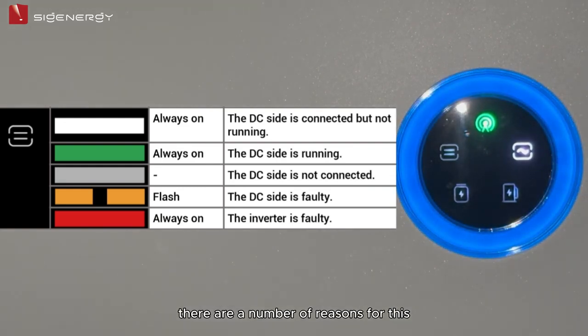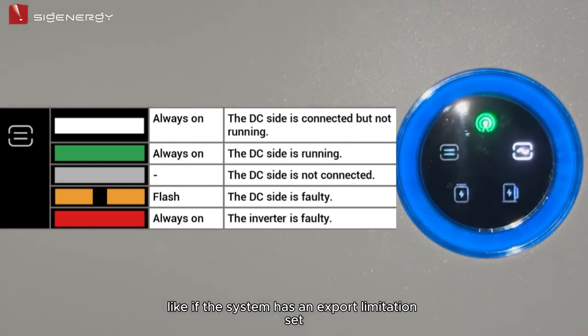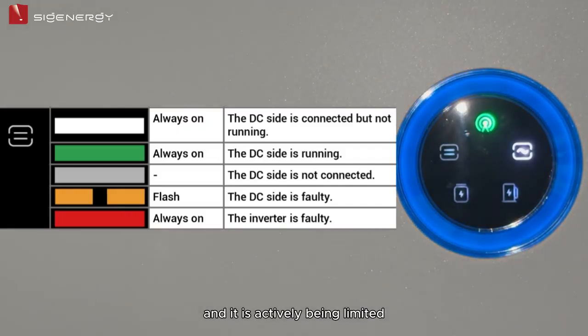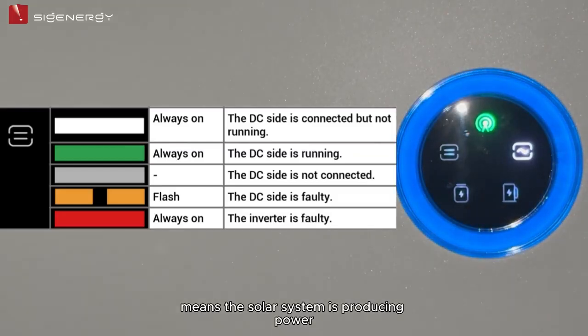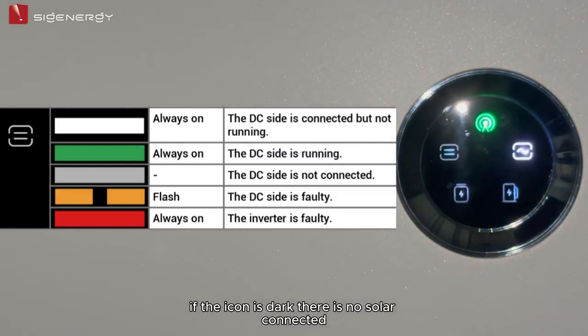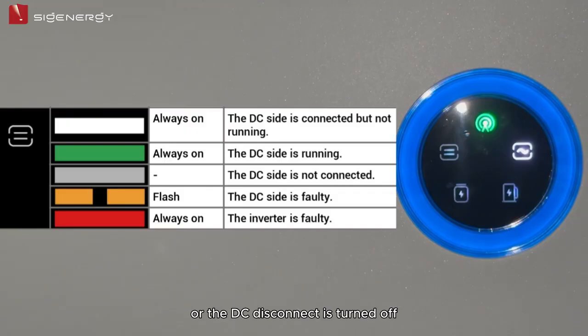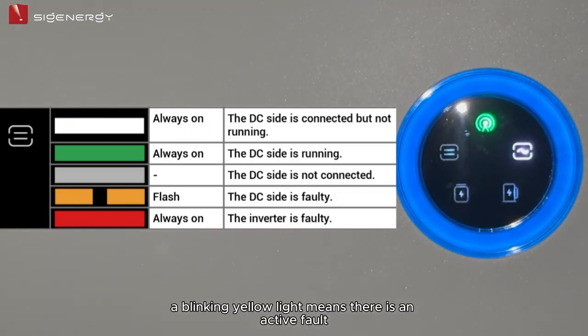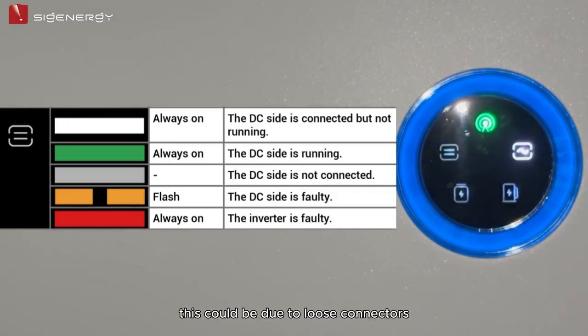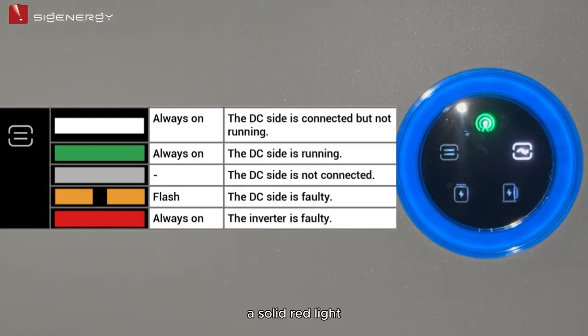There are a number of reasons for this, like if the system has an export limitation set and it is actively being limited. A solid green light means the solar system is producing power. If the icon is dark, there is no solar connected or the DC disconnect is turned off. A blinking yellow light means there is an active fault. This could be due to loose connectors, damaged PV modules, or birds. A solid red light means there is a fault on the inverter.